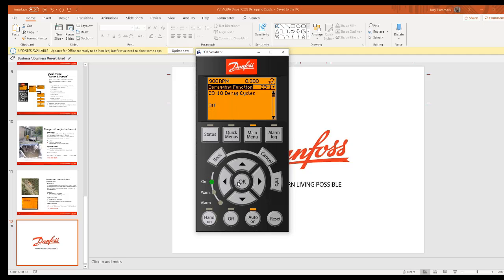And here, like I said, the first parameter, 2910, the cycles is off. So no cycles, the feature is off. The start stop is disabled at the time. And see, the time is 0. It does have a minimum speed kind of preset, or actually the DERAGing speed, excuse me. So you have to set the speed. The off delay is 10 seconds, so there's a default time.